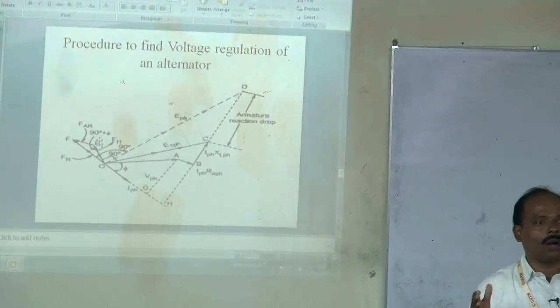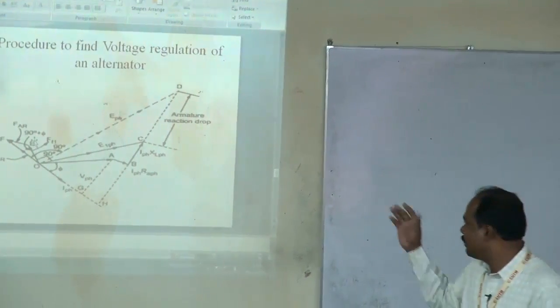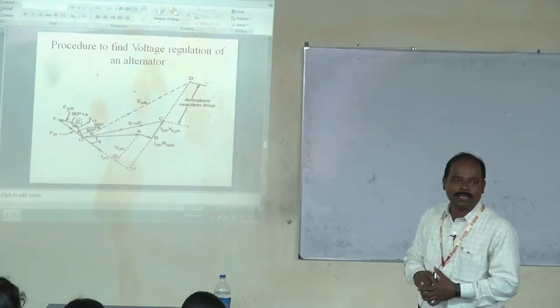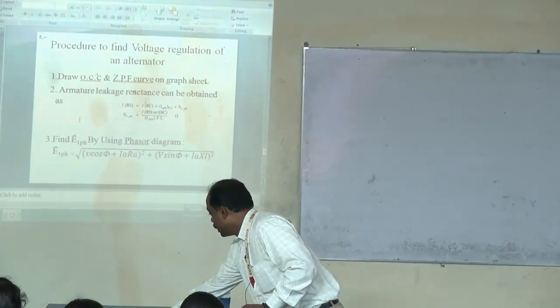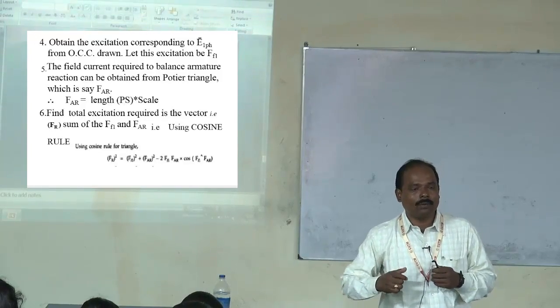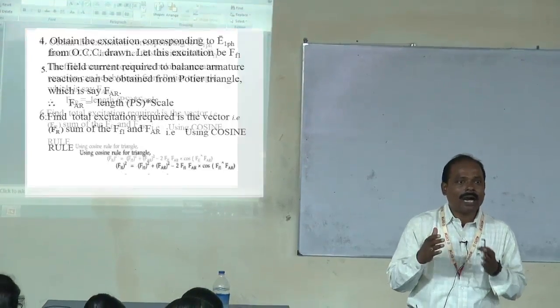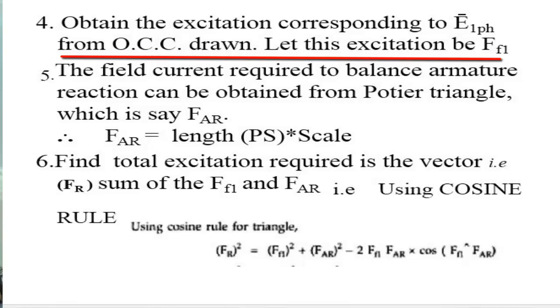Step 4: From the value of E1 obtained, find the corresponding field current Ff1 from the OCC curve. Step 5: Find FAR — the field current required to balance the demagnetizing armature reaction effect — from the length of PS on the graph, scaled by the appropriate field current scale. Ff1 and FAR are now known.